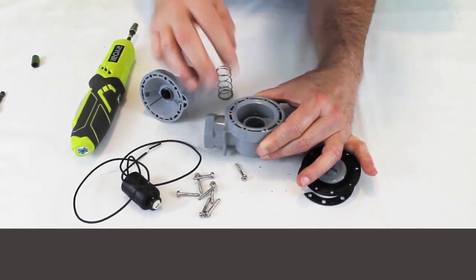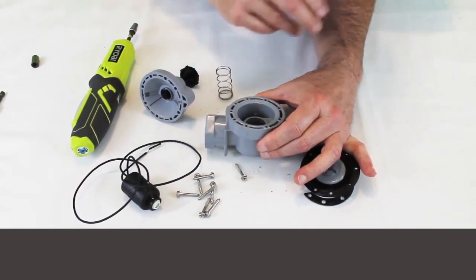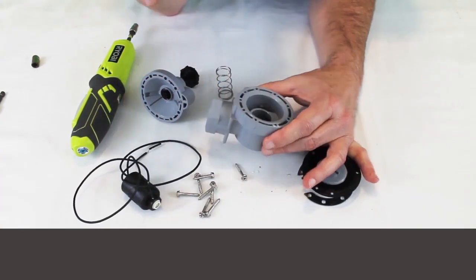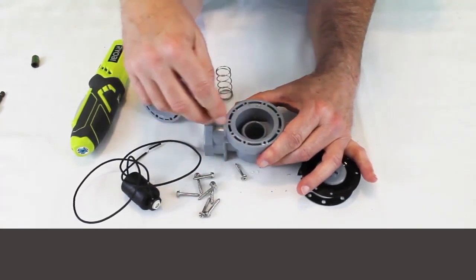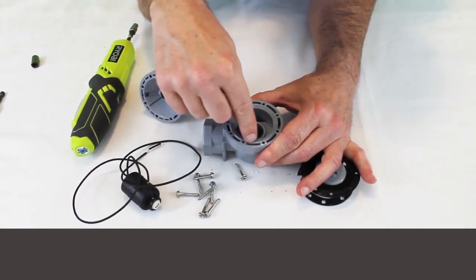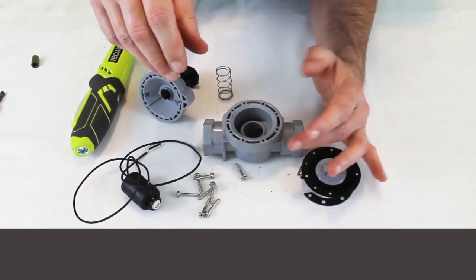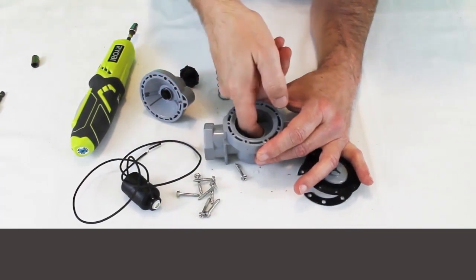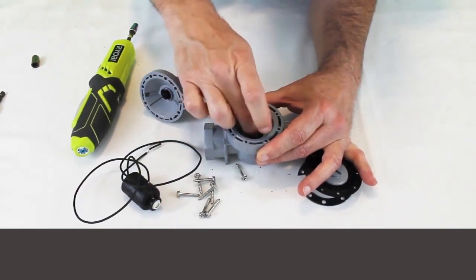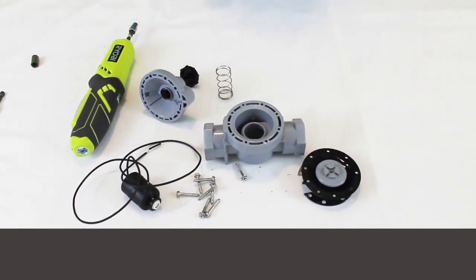Let's take a look here. It's a little dirty on the inside and this is a brand new valve. Maybe something has gotten in, a little bit of dust has gotten down into it in the manufacturing process, or maybe just being in my truck. We're going to check down in here. The diaphragm seat doesn't come out—there's not an extra part for that. We're going to check and make sure that there's nothing down inside the valve that's going to mess it up.